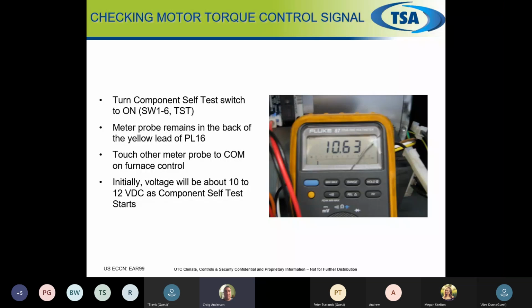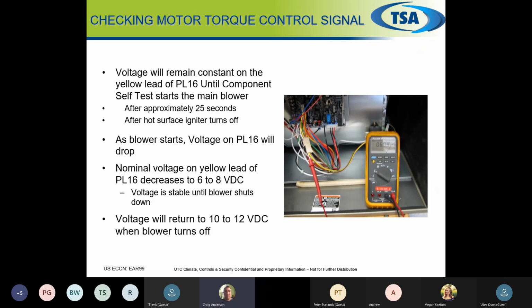So as I said, SW1-6, we're flicking on. We're going to put our probe in the back of our yellow connector, and we're going to go to common on the board. We're going to hit that switch, and then we're going to get ready to go. Before the motor starts, we should have 10 to 12 volts DC. Once it's going through the self-component test, our inducer comes on, our hot surface igniter comes on. Once we're ready for that blower to come on, our voltage on our yellow wire should drop.